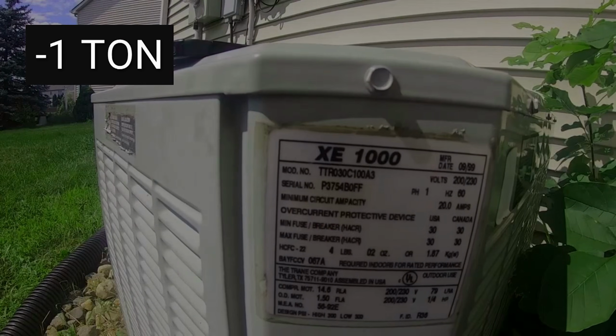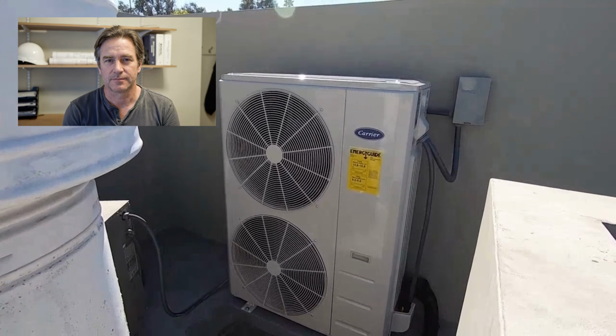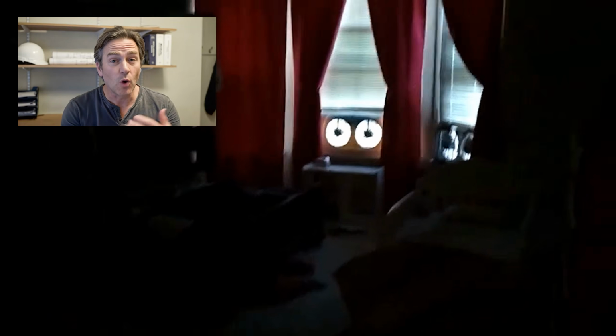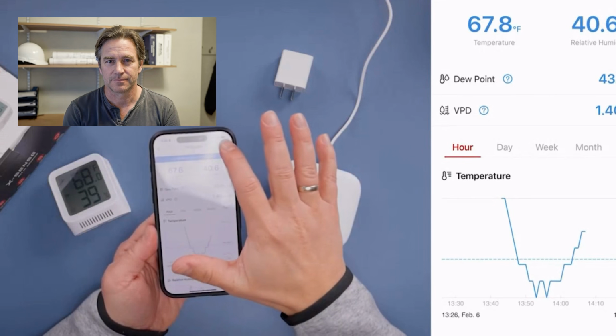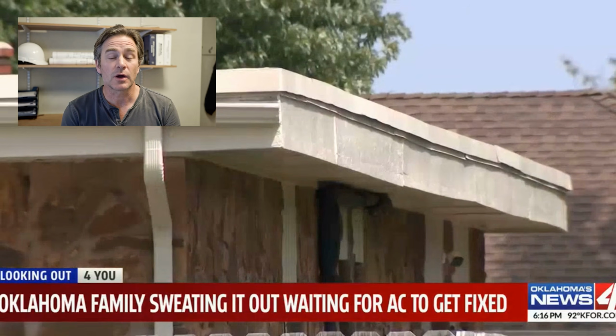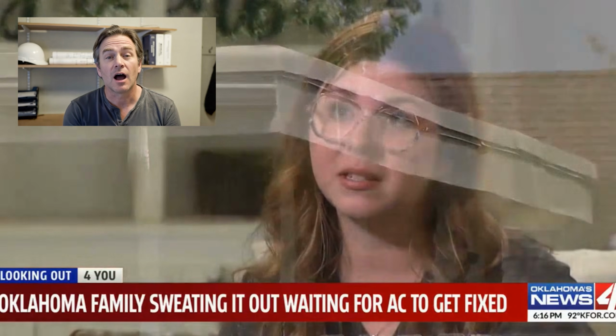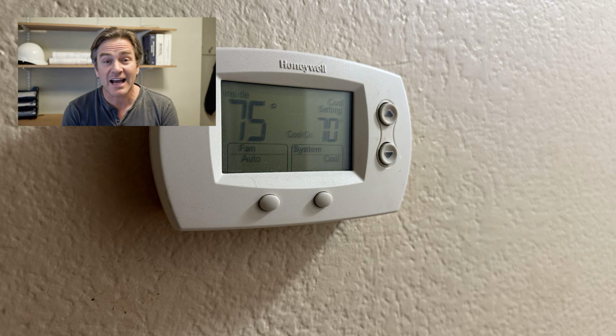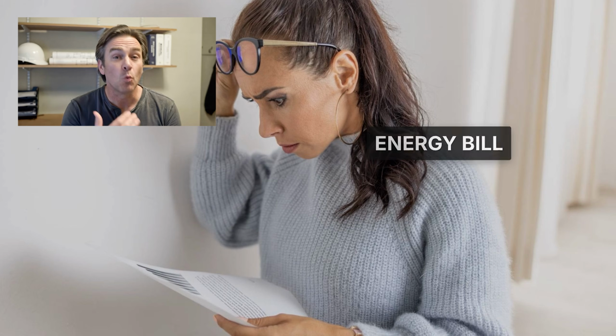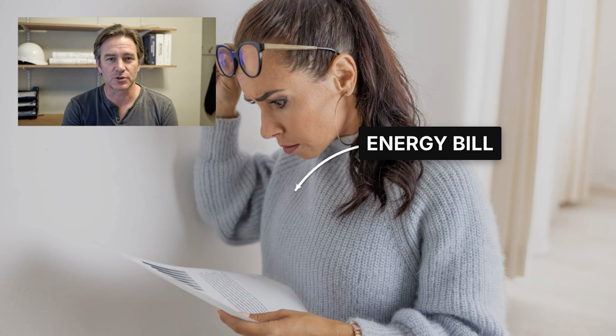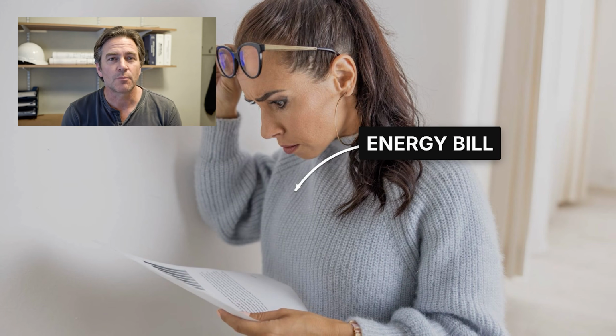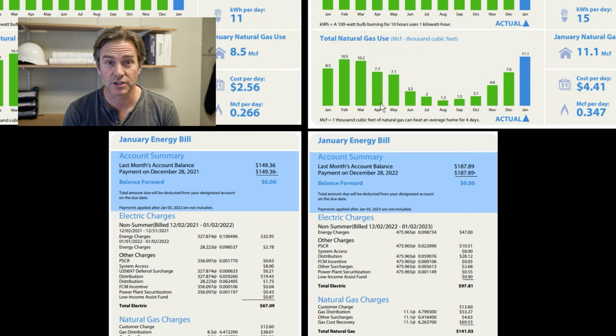The result is a system that is 15 to 25% smaller than your home actually requires. In a 3,000 square foot house, that means you needed a 4-ton system. They installed a 3-ton system. That 1 missing ton is the reason your upstairs bedroom is 10 degrees warmer than your thermostat setting. That 1 missing ton is the reason your air conditioner runs continuously on a 102-degree afternoon and still cannot bring the temperature down. That 1 missing ton is the reason your energy bills are running $200 a month when a properly sized system would cost $120.